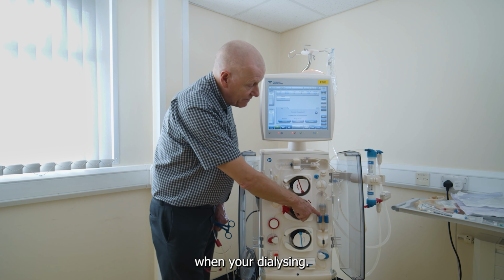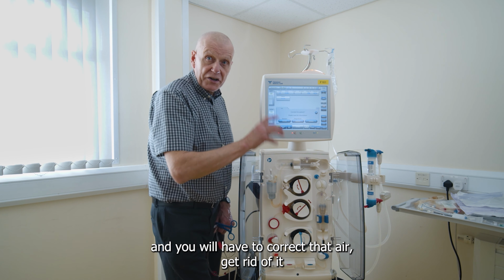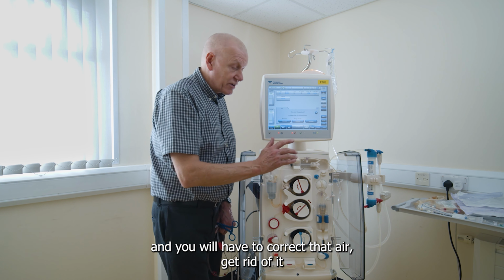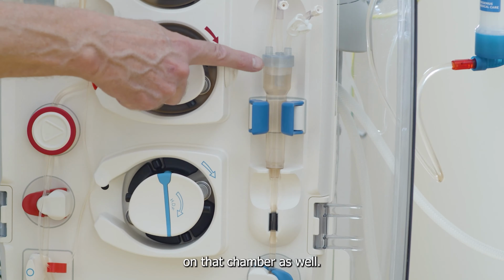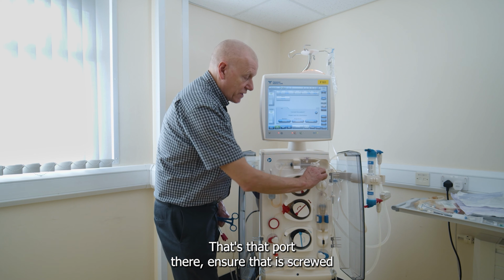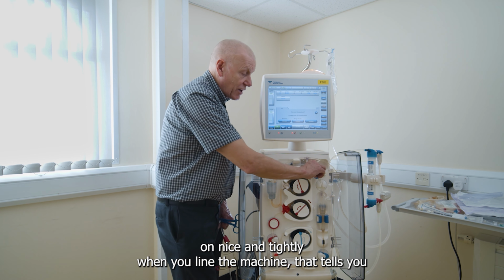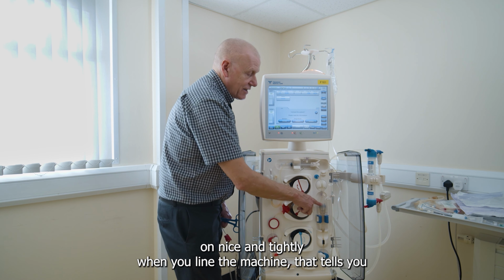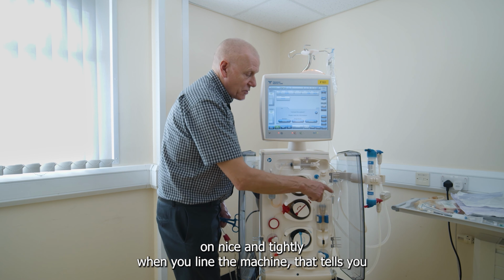If there is air in the blood, the machine will alarm and stop, and you will have to correct that air, get rid of it. On that chamber as well, you also measure the venous pressure. That's that port there. Ensure that that is screwed on nice and tightly when you line the machine. That tells you how good your access is going back into your fistula. If you have a problem there, you will get a high venous pressure alarm, or if the blood should start clotting, you will also get a high venous pressure alarm.